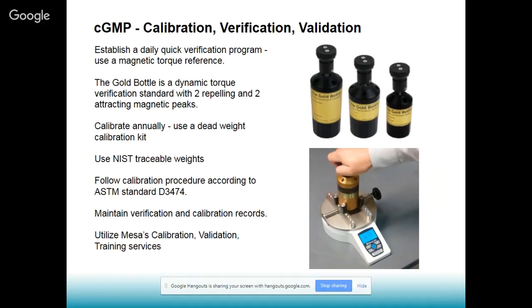Both the calibration kit and the gold bottle, or the weights in the calibration kit, and the torque testers themselves should be on an annual recalibration schedule, where you should verify the calibration with these devices, hopefully even on a daily basis, so you can catch any issues early on. We use NIST traceable weights, and that's required by the standard also. And we follow the calibration procedure according to the ASTM standard D3474.